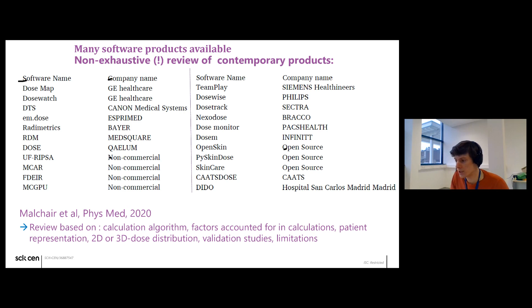The calculation algorithm is actually quite simple. A few software tools use Monte Carlo simulation, but that's not very common. Really, most software tools out there use a simple analytical approach. It's just this formula here that is used for every irradiation event. Each time the X-ray system produces X-rays, this formula is used, and then at the end of the procedure, or during the procedure depending on the system, the skin dose is calculated as the sum over all the irradiation events. The basis of those skin dose calculations is the air kerma, a dose metric output by the X-ray system.